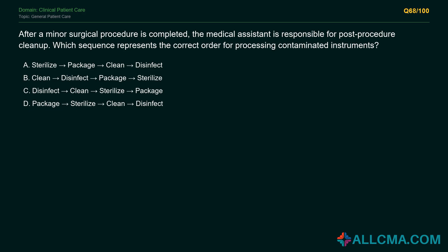The correct answer is B. Instrument processing follows a specific sequence to ensure proper sterilization. First, instruments must be cleaned to remove visible debris, blood, and tissue using enzymatic cleaners and manual or ultrasonic cleaning. Second, disinfection may occur, depending on the process, to reduce microbial load. Third, instruments are packaged in sterilization pouches or wraps. Finally, sterilization occurs in the autoclave. Sterilization cannot be effective if instruments are not first cleaned, as organic material can shield microorganisms from the sterilization process.